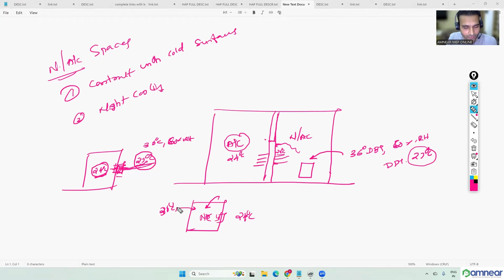For example, suppose the atmospheric temperature is 24, and my room is not air conditioned. Let's say the room temperature is 36 degrees Celsius with 60% relative humidity, so the dew point temperature of the room is 27 degrees Celsius. It is unconditioned space, but at night the atmosphere cools. So if you have glass and building surfaces, the glass temperature will reach near 24, but the room dew point is 27. So when the 36 degrees Celsius room air comes into contact with this glass surface, condensation can come. That is called night cooling.